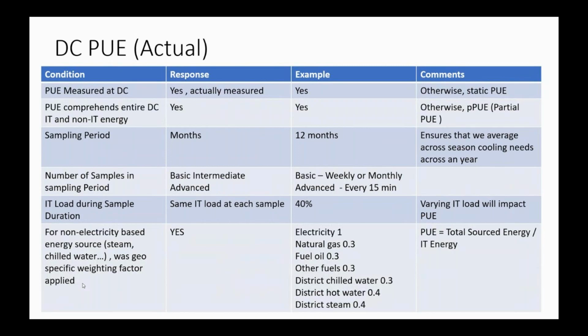What that means is, I live in Oregon, lots of data centers in Oregon, because the climate is cool and rainy most of the time. Maybe one month it gets hot, and in that month they use evaporative cooling, or the chiller kicks in. But if you only measure the months from November through March, when absolutely nothing is running, and you say my PUE is 1.03, you're like, yeah, it is.